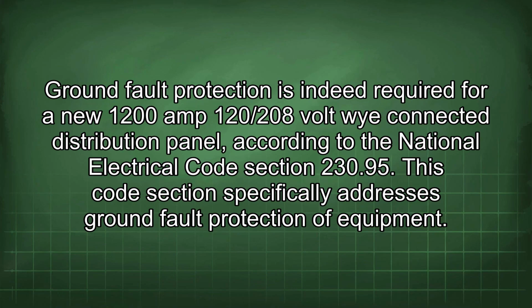Ground fault protection is indeed required for a new 1200 amp 120/208 volt Y-connected distribution panel, according to the National Electrical Code Section 230.95. This code section specifically addresses ground fault protection of equipment.